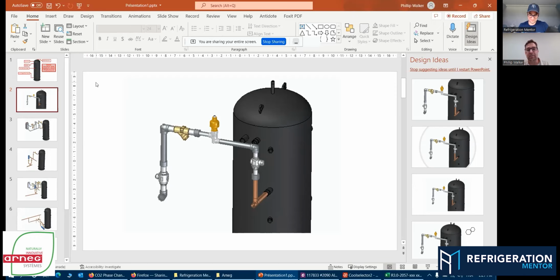Don't forget that little $20 temperature sensor you're putting on the outlet of the gas cooler that's driving a lot of the algorithms to control this valve, okay? So we always put a strainer there. The strainer, you've got a ball valve over here, you can tie off, you can open the strainer and clean it. When we're doing mixed use buildings, I can't tell you, the first 2 projects we did, how critical that strainer was. Because if you're going up 120 feet, and the boys are welding all the way up, you've got a significant amount of debris that could come back down. Well, this strainer saves the valves, right? So this is something we always do in our design, at least.